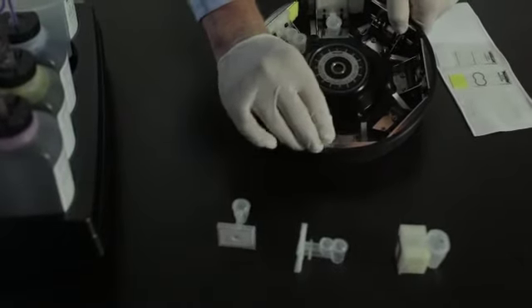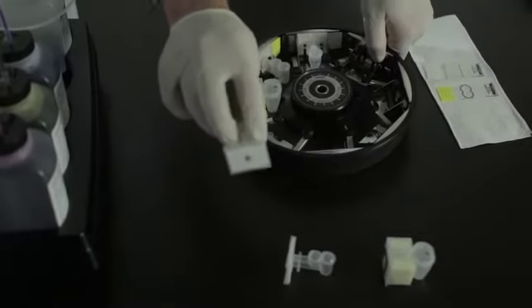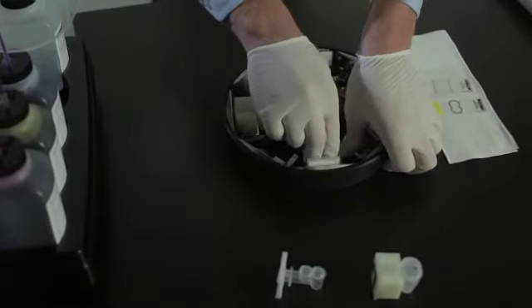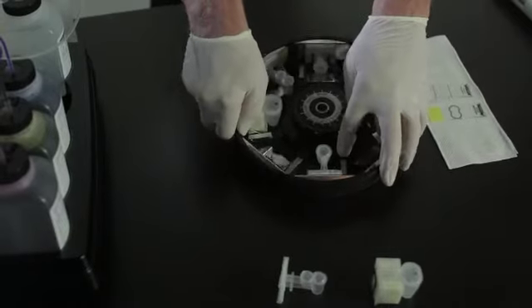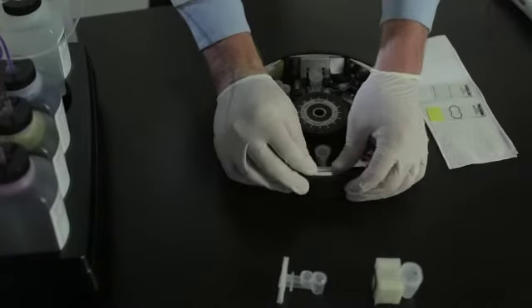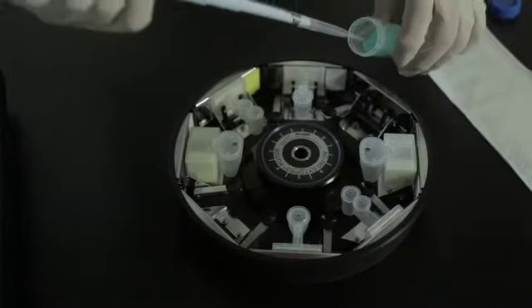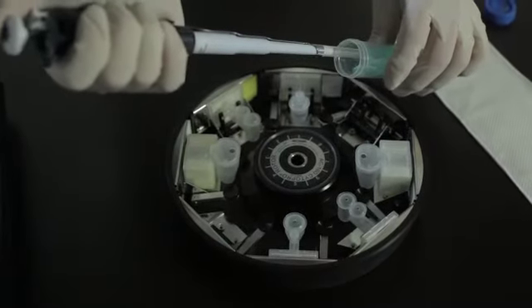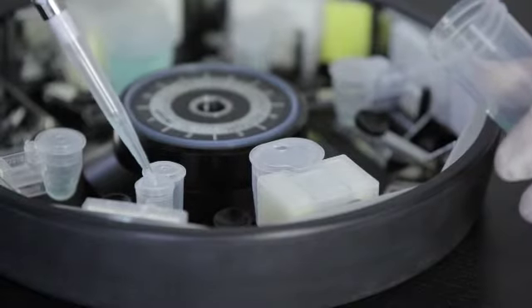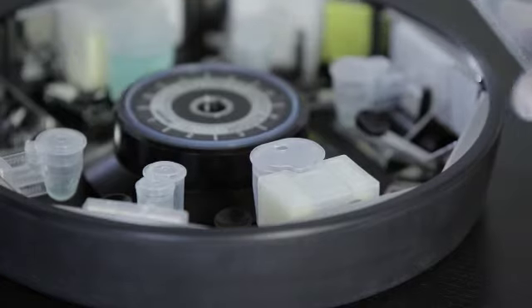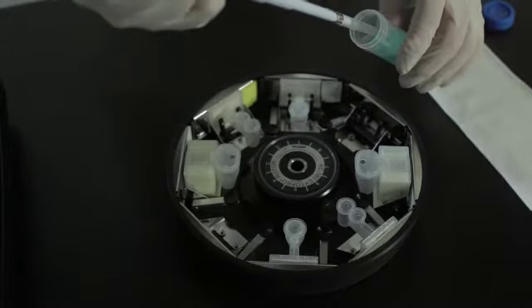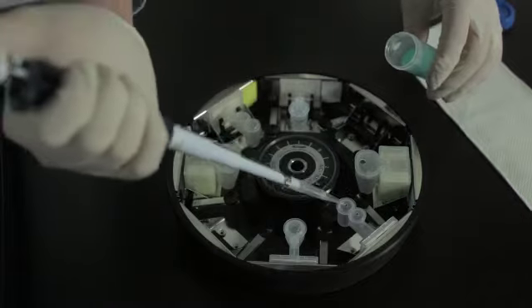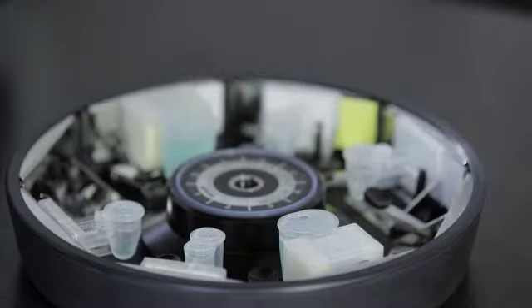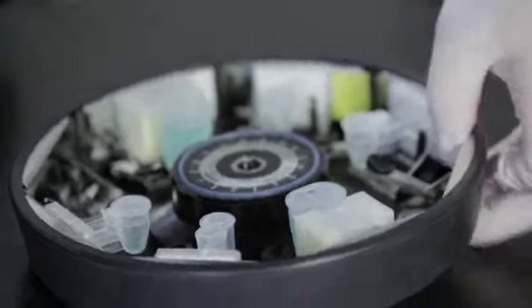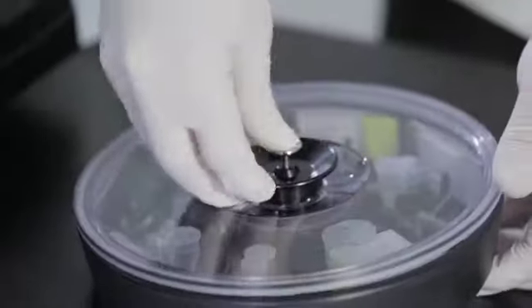Users load the Cyto Pro rotor by loading the microscope slides into the slide holders. Press the black lever to pull back the locking fingers, place the Cyto Pro chamber into place, then release the lever to lock the chamber into place. Users then pipette the samples into the chamber well. Users must balance the rotor with a similar sized chamber on the opposite side of the rotor. Place and lock the rotor lid on the rotor. Depending on the type of samples, users should load and unload the rotor in a biosafety hood.